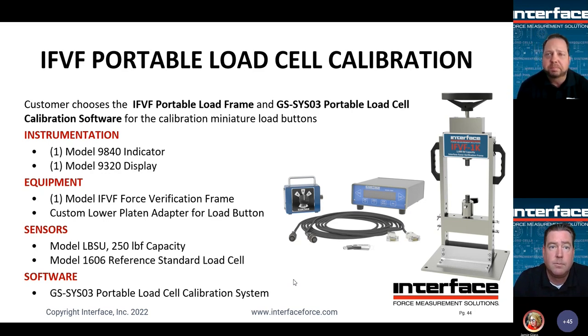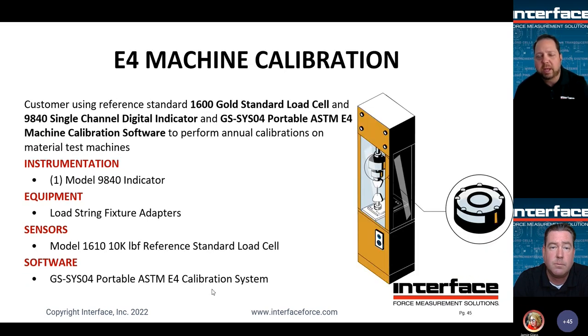So next slide. I would say the most common form of calibration that's out there is calibration of material test frames. And part of that is governed, of course, by the ASTM and the E4 protocol in particular. So that procedure outlines how you go about calibrating a material test frame so that then your test data that you use that frame to generate is valid, right? So we have a lot of customers that have essentially put together kits that they can go and take into material test labs and can perform these types of ASTM E4 specific cals.